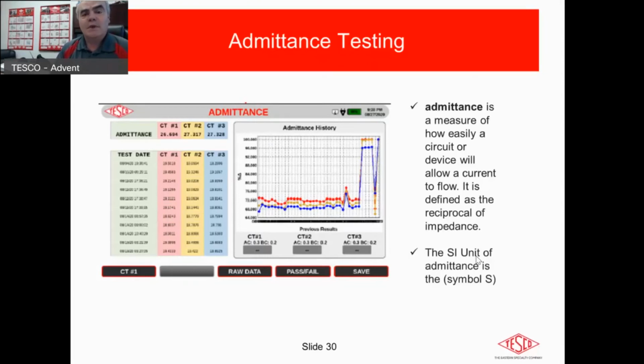So think of an admittance test just like a picture. If someone goes out, takes an admittance test, and a year or 2 years later I go out and get the same answer, I can be pretty comfortable that nothing has changed in that circuit. If I get a different answer, it doesn't mean that things are bad. It doesn't mean that I've got a problem. It means that something changed. And now I know that I have to look a little bit harder. What changed? Is it just a loose wire? Is it corrosion? Did somebody add something to this circuit?